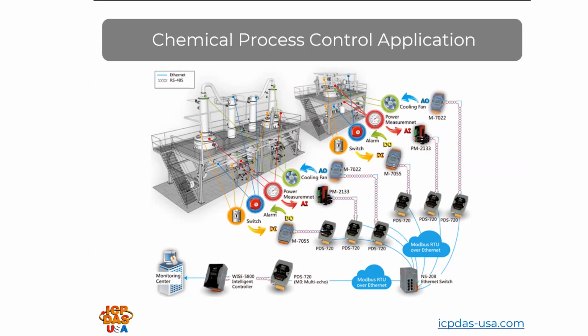The monitoring center allows you to see the status of the system through a web browser on a screen, which pulls up the web server in the WISE5800. The PDS720 is connected to WISE5800 over RS-485, and it's connected to the NS-208 Ethernet switch over Ethernet cabling. The NS-208 Ethernet switch is connected to the PDS720 serial to Ethernet device server over Ethernet cabling.